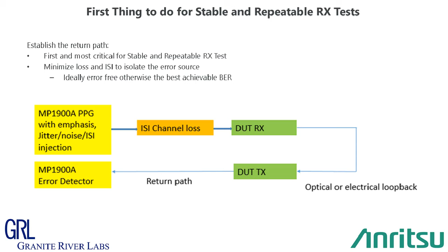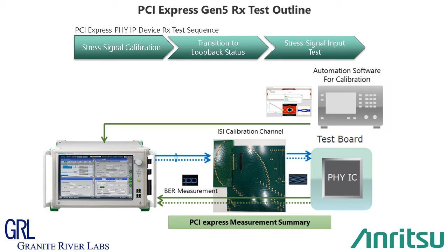So the contribution of the error is very, very minimum. So let's talk about the actual calibration process. You only need this BER tester, compliance board, and scope for the calibration, scope for response time measurement, and then the DUT. That's it. The calibration at TP2, stressed eye calibration, is the most time-consuming and difficult portion. And again, same recipe: you need to achieve this very closed eye using SJ injection, RJ injection, DM, CM injection, then the ISI board. There is a CTS to describe the details.